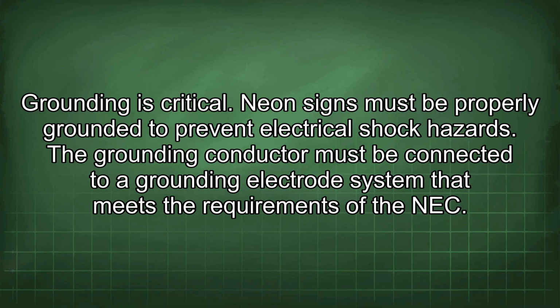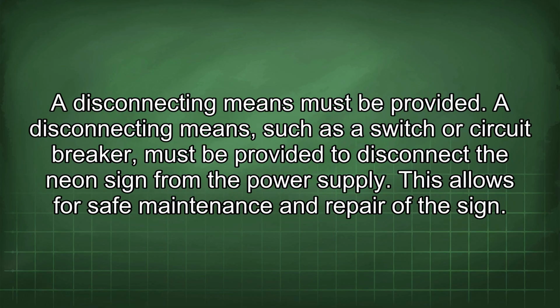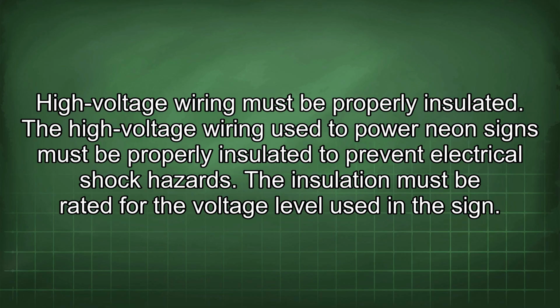Grounding is critical. Neon signs must be properly grounded to prevent electrical shock hazards. The grounding conductor must be connected to a grounding electrode system that meets the requirements of the NEC. A disconnecting means must be provided. A disconnecting means, such as a switch or circuit breaker, must be provided to disconnect the neon sign from the power supply. This allows for safe maintenance and repair of the sign. High voltage wiring must be properly insulated. The high voltage wiring used to power neon signs must be properly insulated to prevent electrical shock hazards. The insulation must be rated for the voltage level used in the sign.